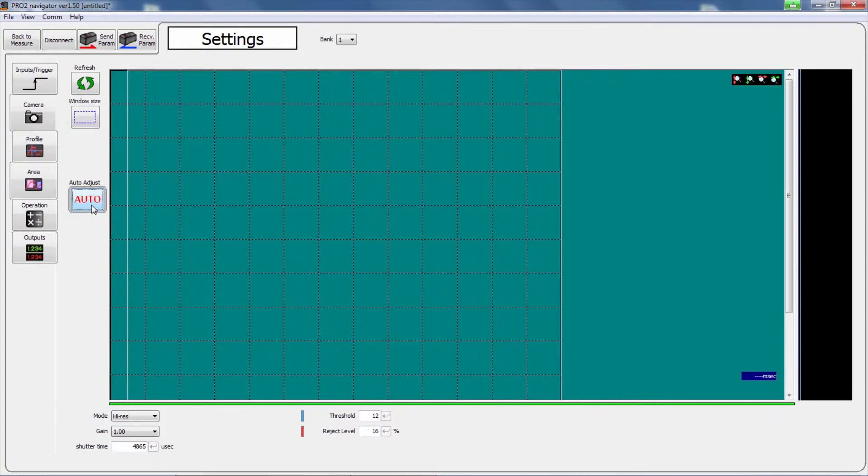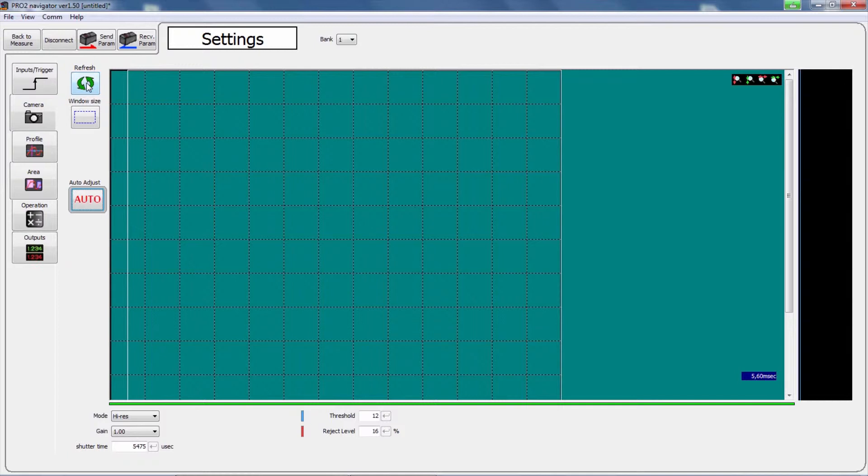Click the auto adjust button to automatically set the shutter time. This function can only be used in high resolution mode. For difficult surfaces or different colors in the measurement target, please refer to other camera modes, which are described in the instruction guide.